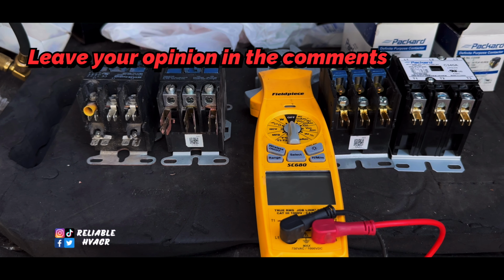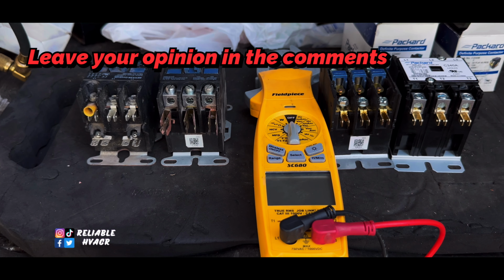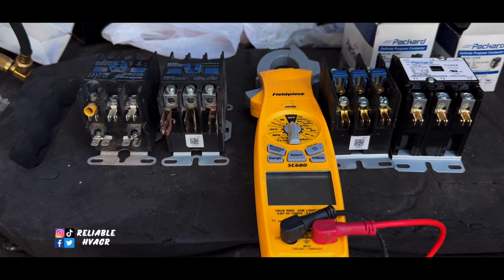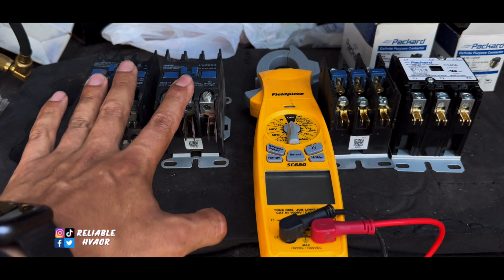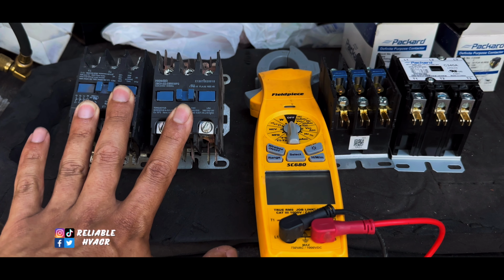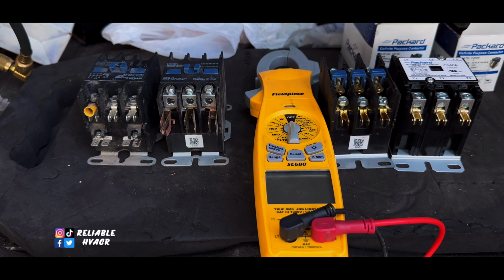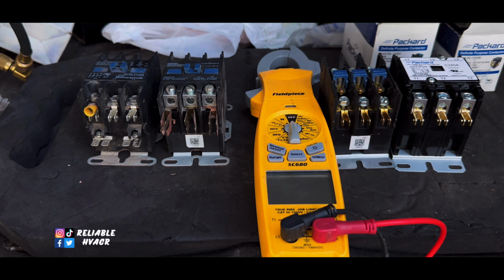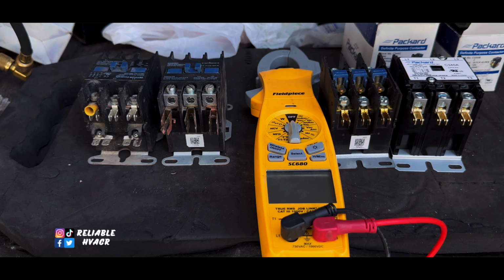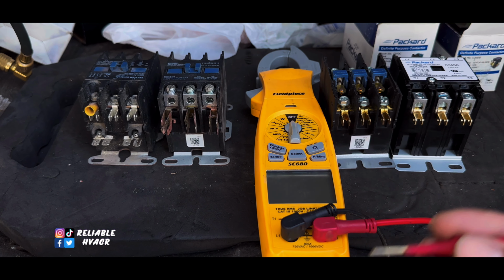So I don't know the science behind it. Some people were saying it pulls 3 amps if you're under 8 ohms, which I'm not sure about. But transformers vary on amperage and voltage, because I also deal with walk-in coolers and freezers, which have 208/120 volt coils. Like the transformer in this video, it doesn't trip on 3 amps, it trips on 4.5.